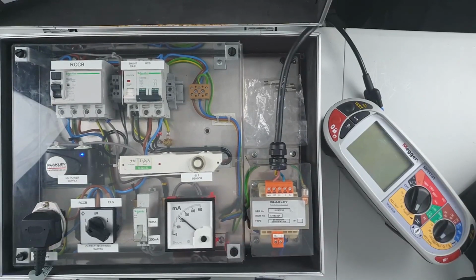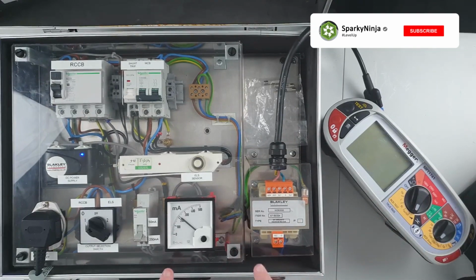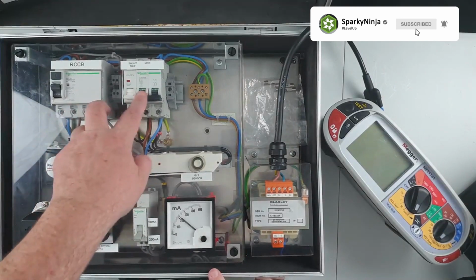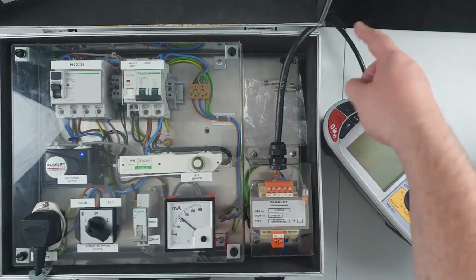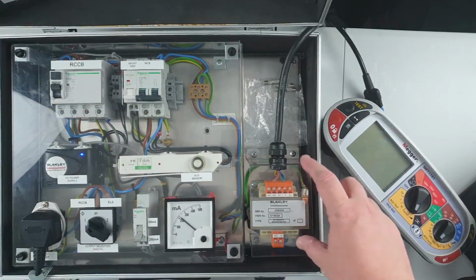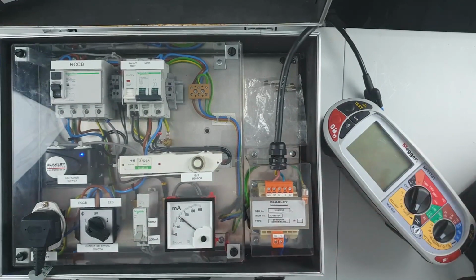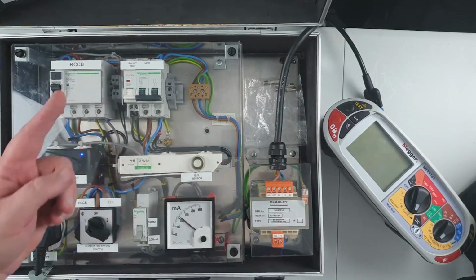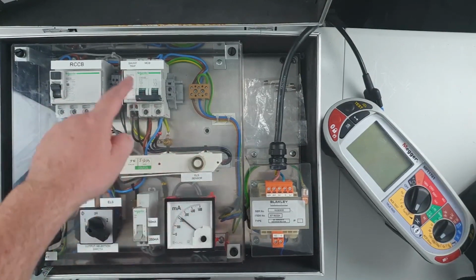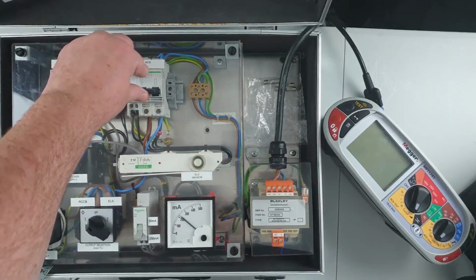Okay, so here I have a test rig which has been manufactured to illustrate the impact of DC leakage currents on AC RCDs. With a power supply coming into an isolating transformer, that's just going to protect any other RCDs in this building from operating while I do this. It then goes through to a selector switch, which will select between the RCCB or the earth leakage sensor and shunt trip to this double pole device here.